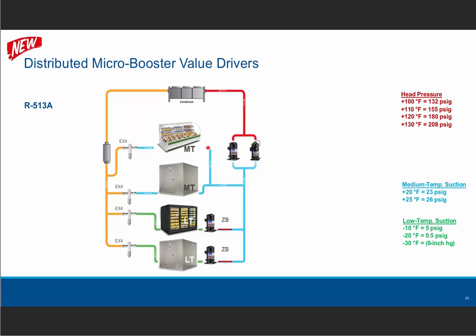There are no EPRs here. There are no solenoid valves here. There is nothing to cause pressure drop, to add extra leak potential and mechanical failure. We're trying to keep a low pressure drop system to increase efficiencies and optimize performance and make sure oil and refrigerant flows unrestricted. But the advantage here of the low temp down here is that if you leave this compressor off and you enable the electronic valve, this compressor design is that flow can go right through it.